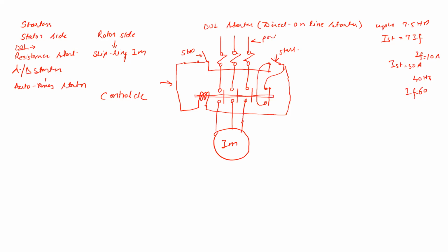Now, as soon as we switch on the supply, the current flows into the plunger. It will attract in this direction, so this contactor is going to close. The supply is connected with the induction motor. And this is a normally open contactor, so it will close the contact, whereas the current is going to flow from the external contactor, and the motor will remain in the running position.